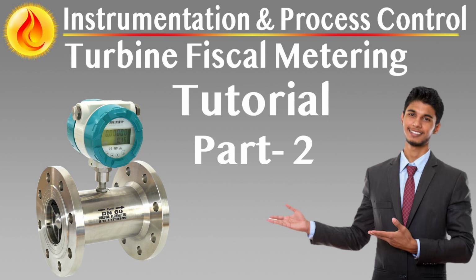Vents and drains must be provided at all piping high and low points with visual indicators on each drain to confirm fluid discharge. The structure must retain full integrity independently of the process or measurement equipment mounted to it. Material compliance with process compatibility.